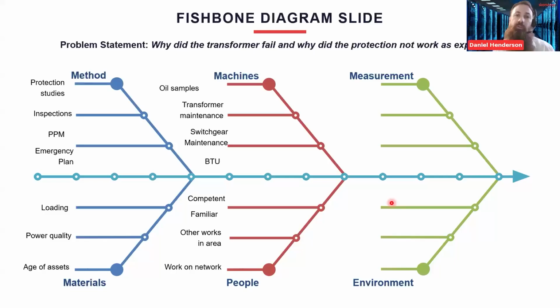It's a good point because typically electrical equipment is designed to be safe in its standard operating configuration. So if anything is going to go wrong, it's when you're taking it outside of that, maybe for switching or maintenance. So it's a really good point. There was no work on the network going on. From an electrical perspective, there was nothing happening. There were no isolations or switching or anything like that. So nothing on the electrical network. Works on site.